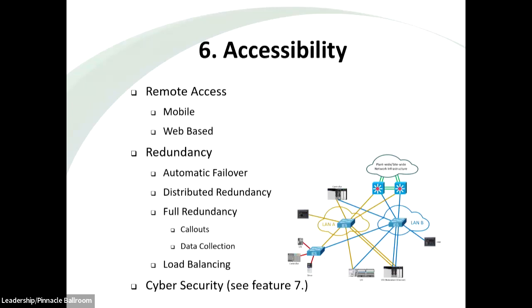Load balancing is a feature that comes with a redundant setup. It means that if your SCADA server's processor is constantly working hard to get data from remote sites and is nearly maxed out, maybe your backup server should take over some of those tasks. Since it's sitting there helping, why not have it help collect and process data, sharing the load of what you're asking your control system to do? Not every SCADA system can provide this feature, but it will become more important in the future.